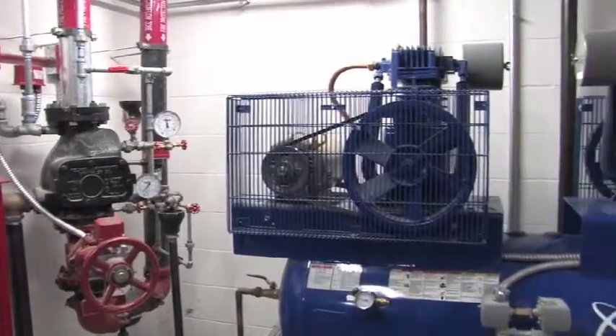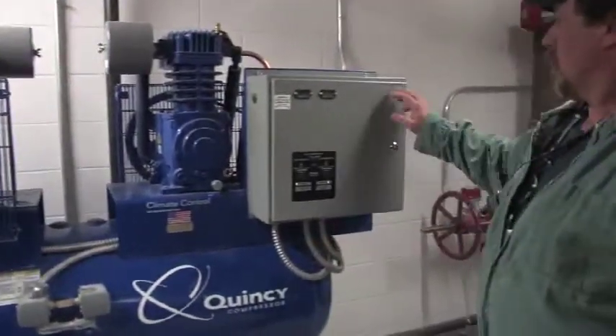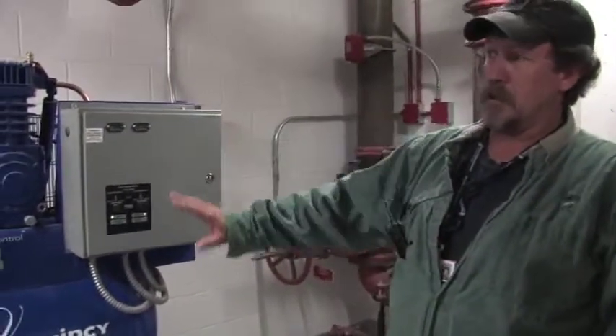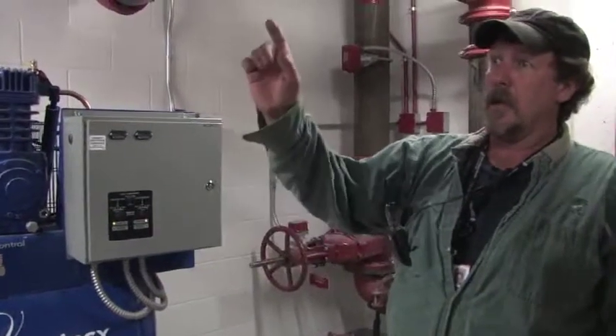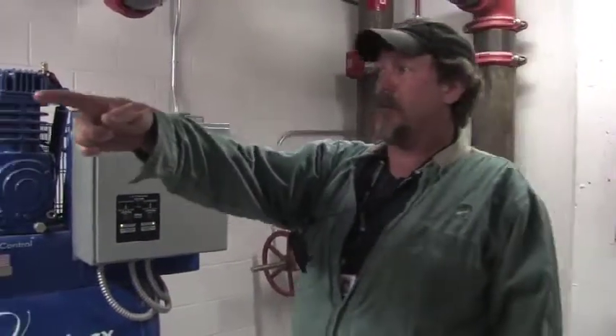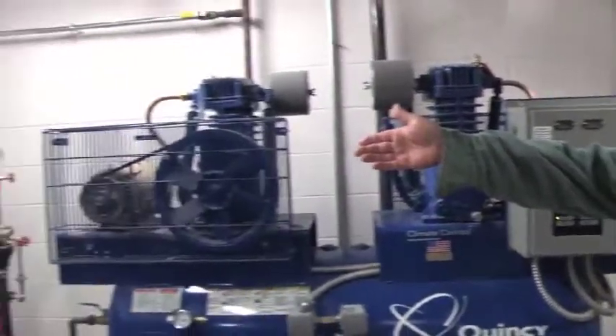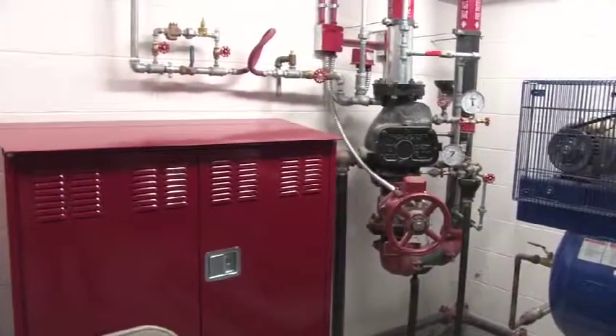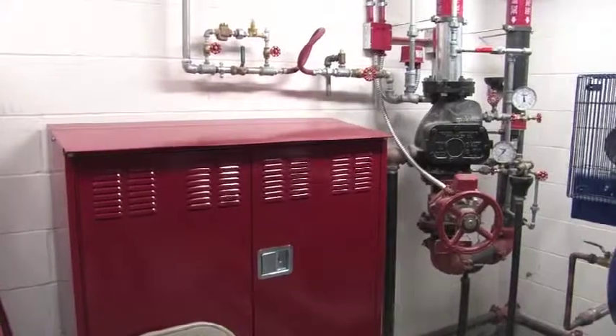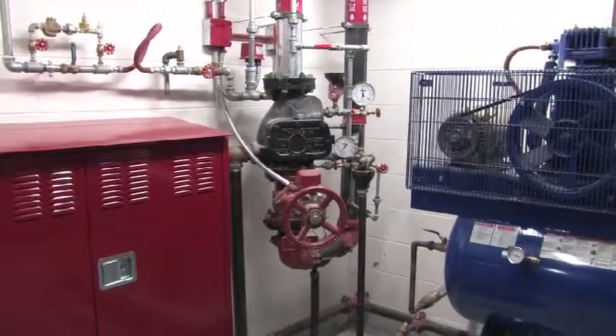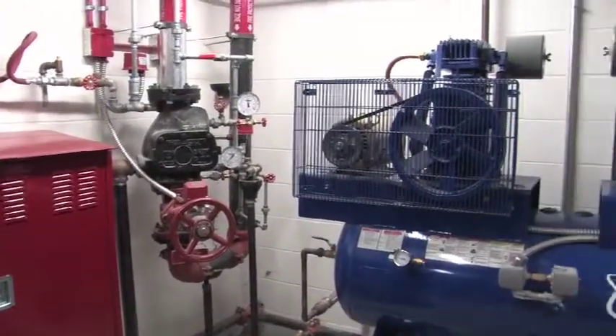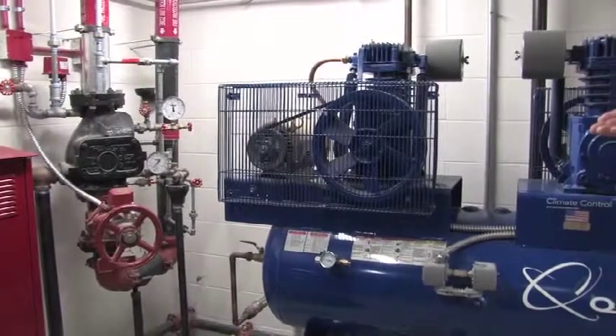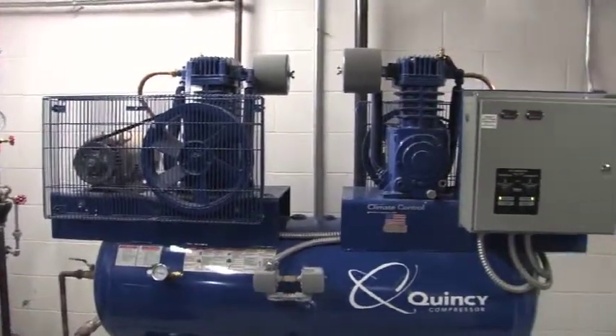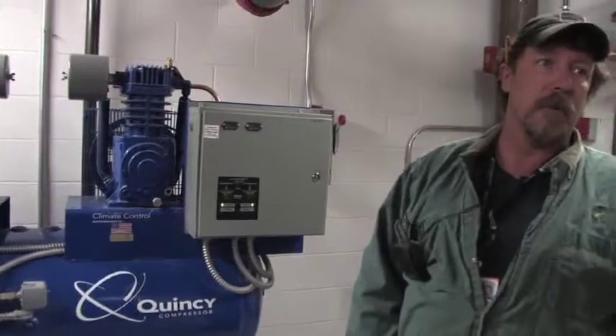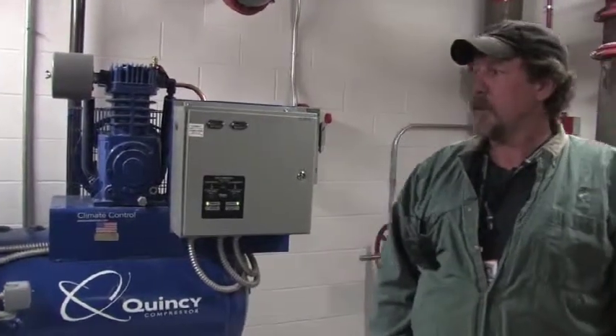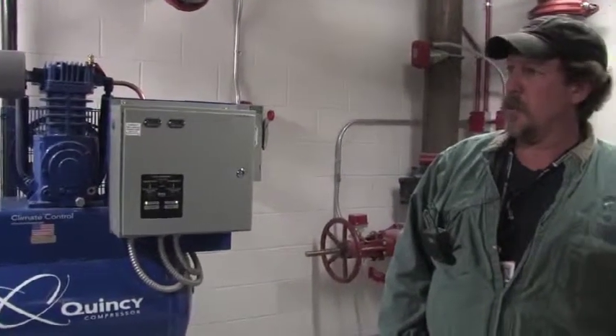So I think the air compressor here is set between 60 and 80 pounds is what this will come on at. And we have air maintenance devices hooked up to all the three different systems requiring air. On this one here, we're pushing through about 45 pounds to hold back the water pressure on the dry system. And upstairs, it's a lot less because they're just pre-action valves. But that's about what we got right here.